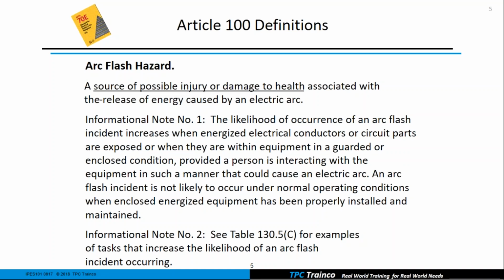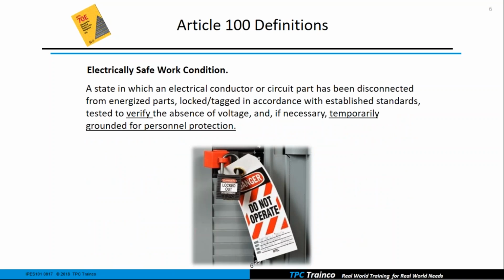So in definitions, arc flash hazard, they now put in a source of possible injury or damage to health. So I want you to understand that the arc flash is a tremendous amount of heat, and they gave us this definition to help clarify that. Electrically safe work condition in definitions has also been changed just a little bit. And in a minute, we're going to see that there are even more steps now to achieve that electrically safe work condition. In the 2015 version and prior editions, there were 6 steps. Now there are 8 steps.